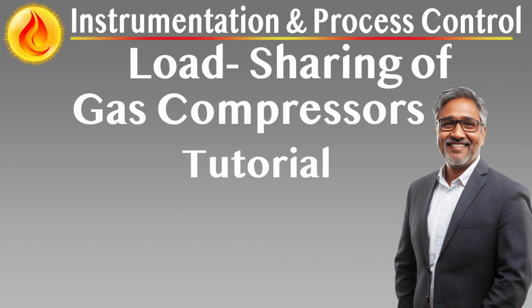The station controller, responsible for primary capacity control, acts as the central command unit, calculating control responses from the deviation of a key process variable, such as discharge pressure or header flow. Its output signal is distributed across all compressors, enabling seamless cooperation between individual performance and protection controllers.